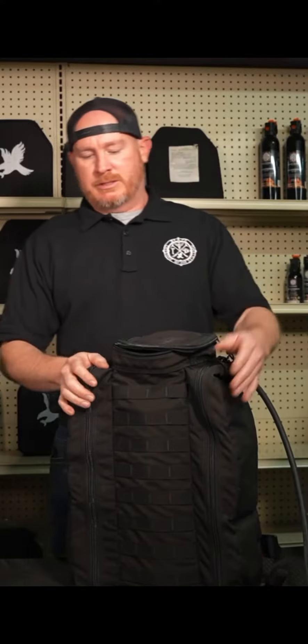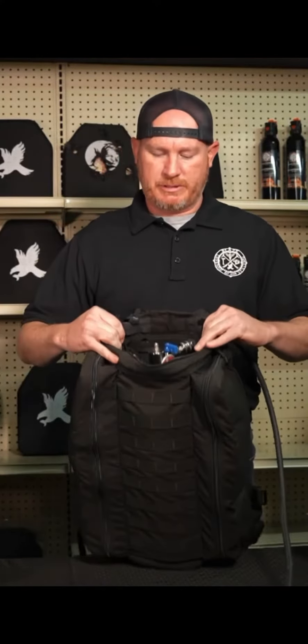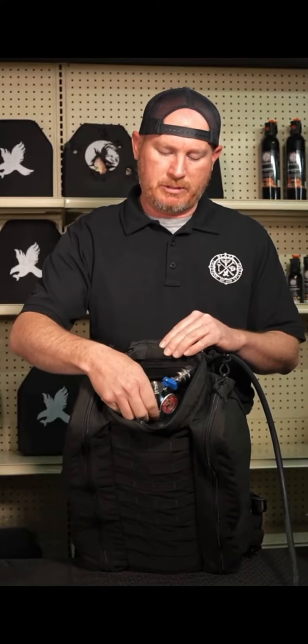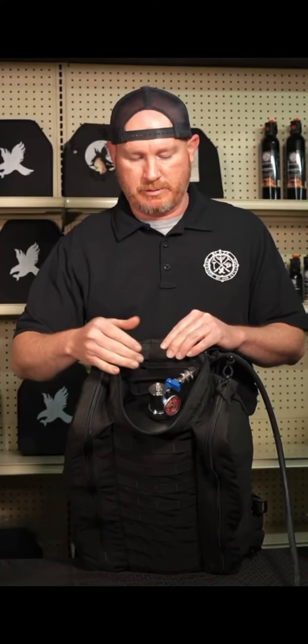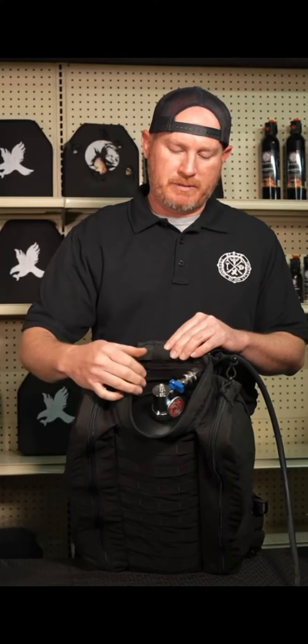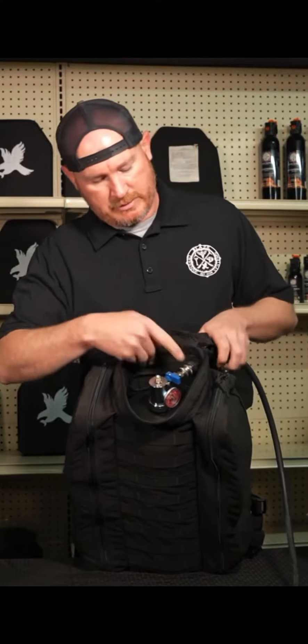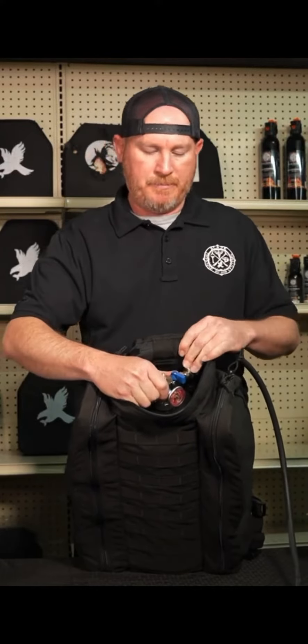This is the most latest rendition. It's a one-and-a-half gallon cylinder, as you can see right here. It's got a built-in Schrader valve on top. The cylinder is stainless steel. If you were to unscrew this and pull it out, it's got a flexible dip tube where you can actually lay on your side and deploy the agent, and it will still dump the contents of the cylinder. It's got a 150 PSI gauge on it and an on/off valve. It connects and disconnects via a quick connect.